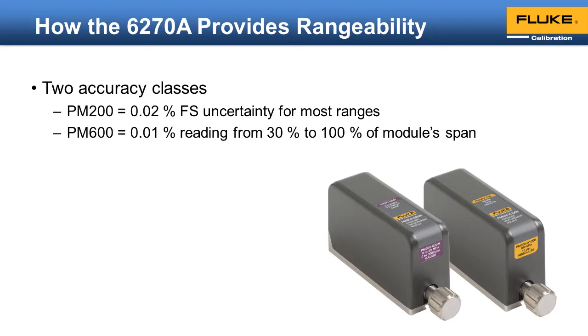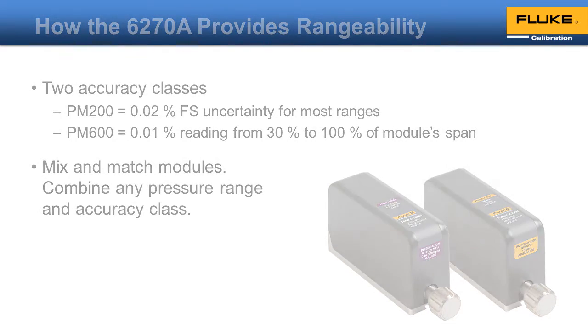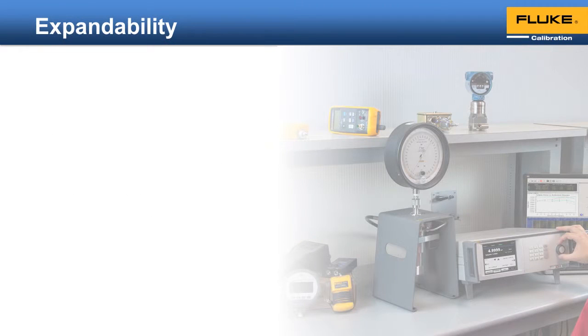Flexibility brings rangeability. With the 6270A, you can mix and match modules as needed — combine any pressure range and accuracy class so that you can meet your needs exactly. Your calibration needs change over time. With a traditional non-modular pressure controller calibrator, it is next to impossible to change the range or accuracy class. With a properly designed modular system, the pressure controller calibrator can grow with your needs.